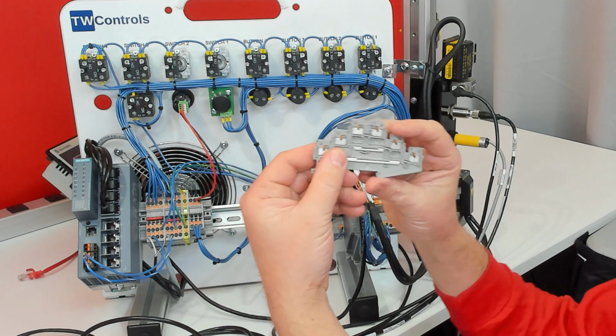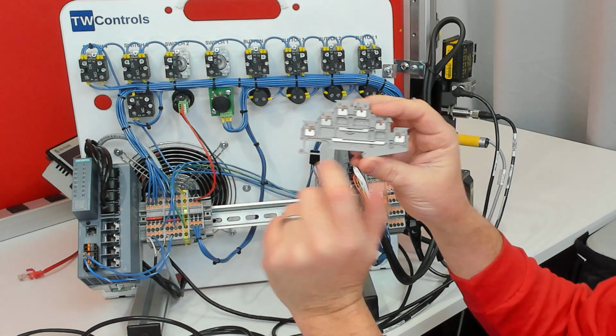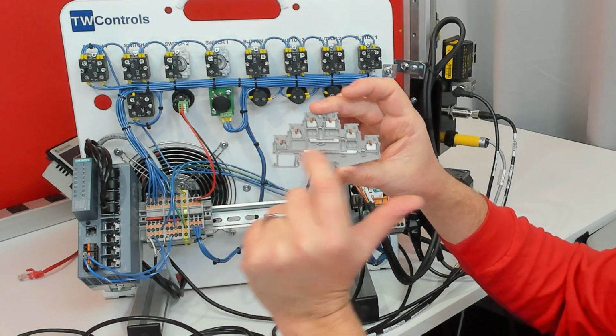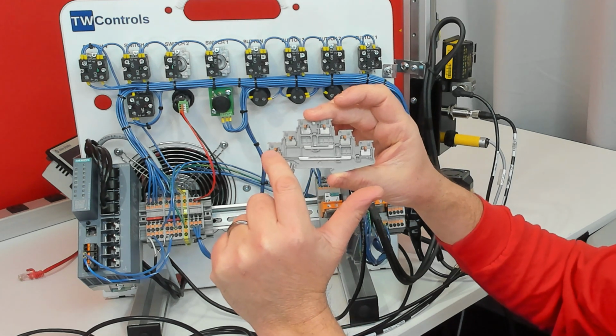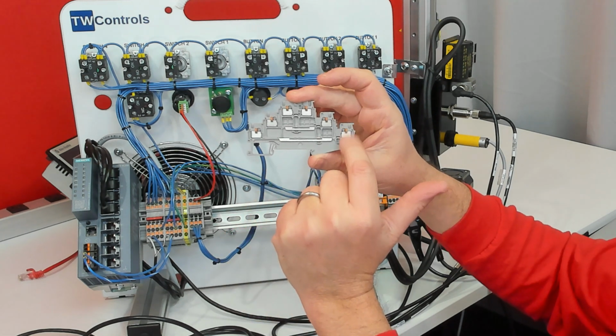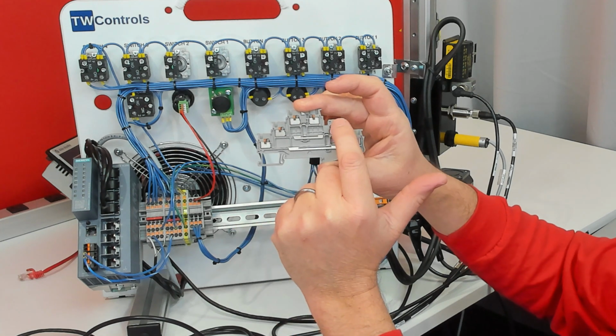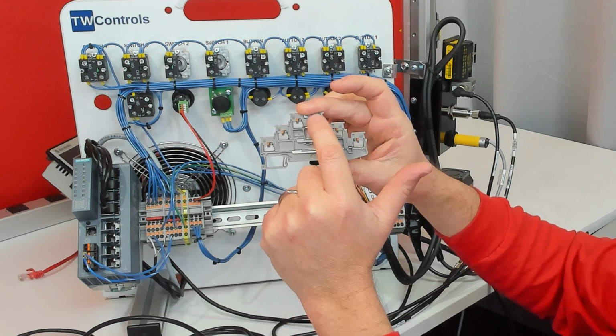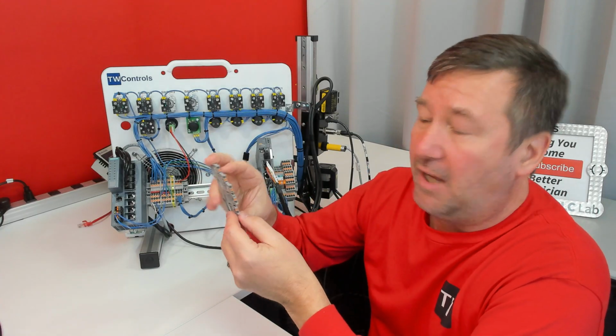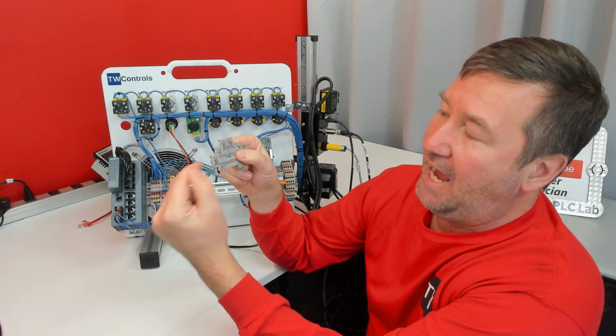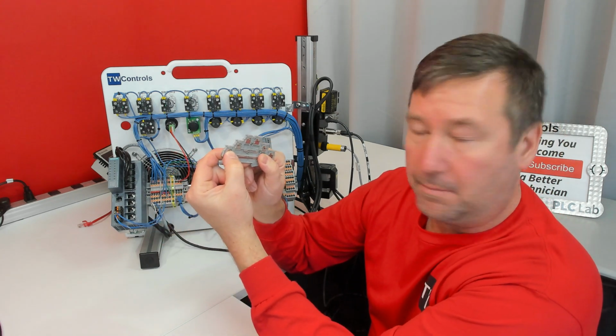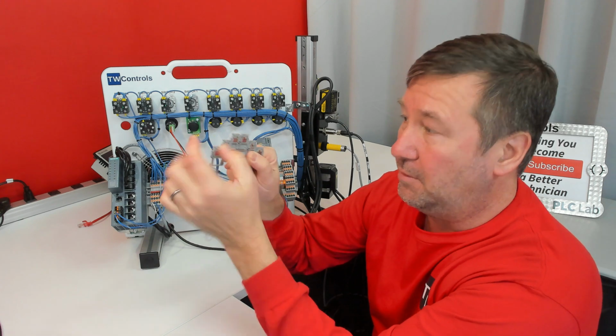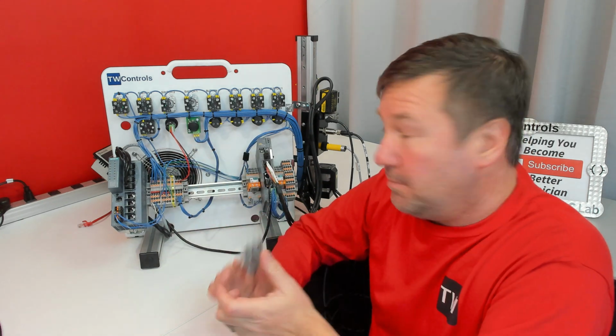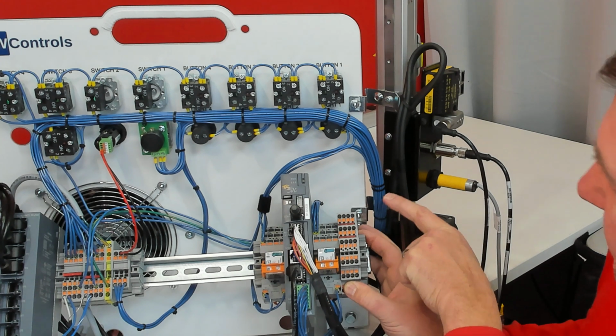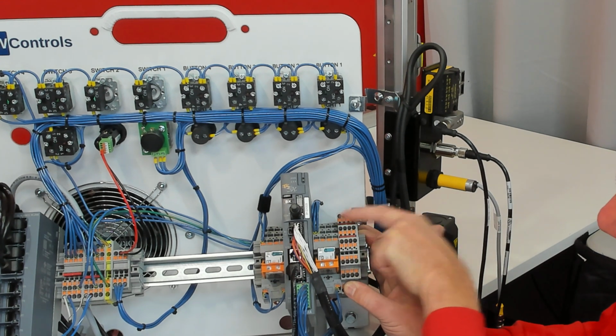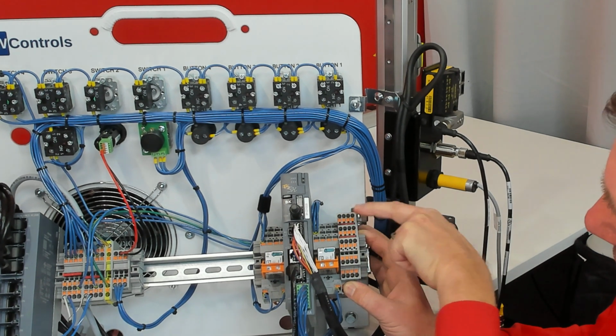Now these look a little bit different. Notice they're stepped. And when you see them stepped like this, this means that only the ones on the same level are connected. So this one is connected to this one. This one is connected to this one. And this one is connected to this one. And this is a really common terminal block that you'll see on sensors because we can power our 0 volt on the bottom one, our plus volt on the middle one, and the top one usually is actually our input or output.